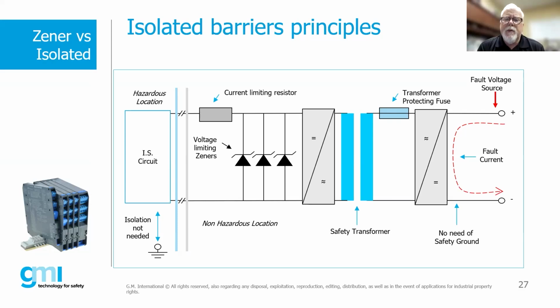Well, is there any application where a Zener barrier may be required where maybe this one couldn't do it? And it really boils down to, in many cases, you can use either. You can use a Zener, you can use a galvanic. However, there may be some instances where I do need to have that direct connection to my end device, and I cannot, for whatever particular reason, use a safety transformer. It has to be a direct connection into that field device. So in those instances, maybe a Zener barrier is the only way you can go. Because I've run into a few applications, not too many, where you really don't have an option. You must use a Zener barrier. But in most cases, you can use either or.